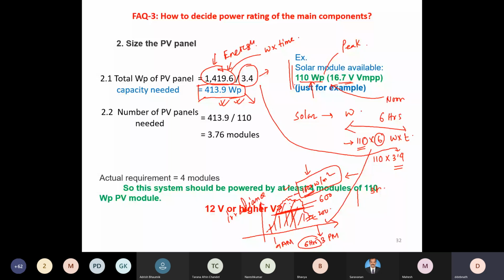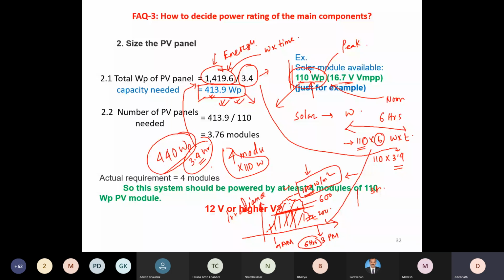In our example, the solar module rating is 110 watt. If I need a total of 400 watt kind of power, and I have 110 watt modules, I need around 4 modules. 4 modules of 110 watt each gives me 440 watt peak power. Over the day, I may get this power for roughly 3.4 hours, which gives me the energy. Remember, this is not simply 6 hours or a fixed time like 9 to 4 or 6 pm; it's a ratio you take from the map.